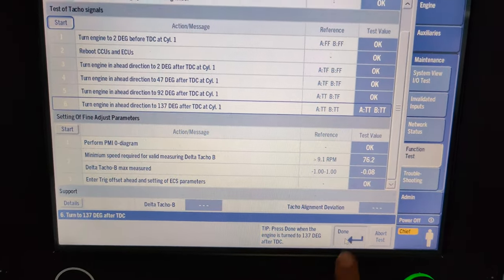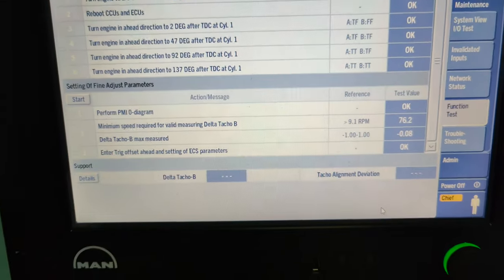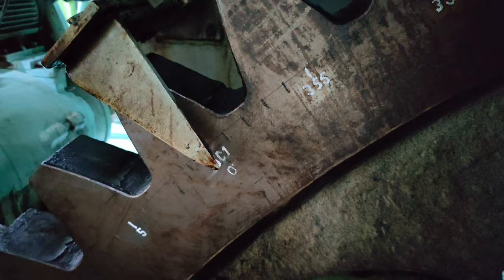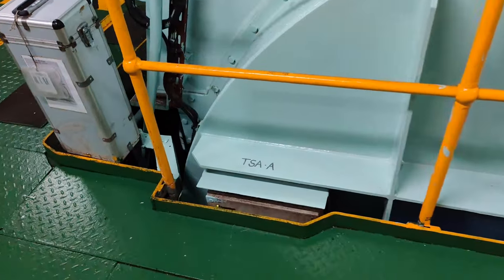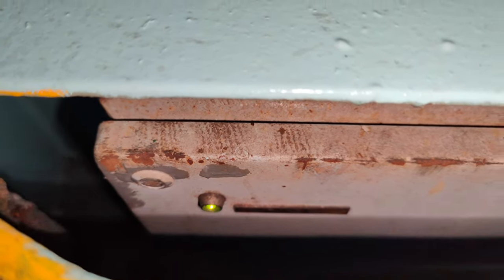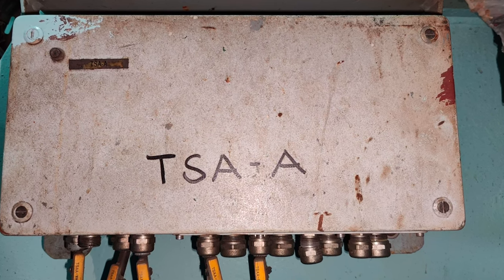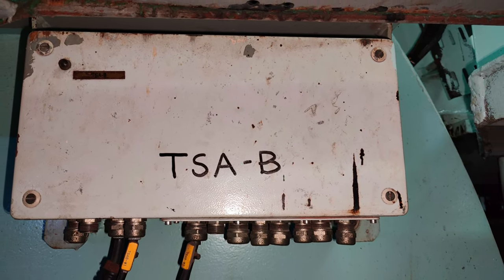Once all steps are completed with all test value statuses OK, you need to validate the functioning of the tacho signal amplifiers. Start turning the engine from 2 degrees before TDC. At exactly 0 degrees, the LED on tacho signal amplifier A box must be on. Continue to turn the engine in the ahead direction; at exactly 45 degrees, the LED on tacho signal amplifier B box must be on. Upon further rotation, at exactly 180 degrees, the LED on TSA A box must go off, and at 225 degrees, the LED on TSA B box must go off.